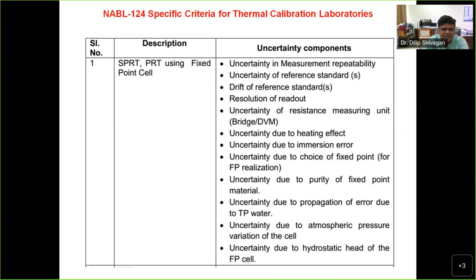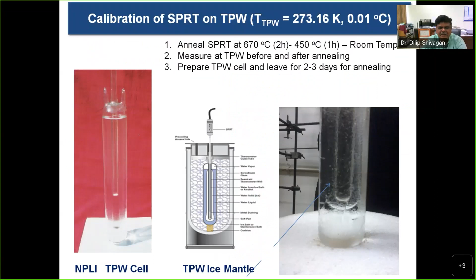So that you can estimate the drift. Platinum resistance thermometers are very good because they are very linear, but still you can see that at lower temperature they go toward the Debye temperature, meaning resistance will not increase linearly, and at high temperature also they will have some losses. So ITS 90 has given very standard equations for how we have to interpolate. Basically, you have to measure first at the fixed points and evolve these alpha, beta, gamma coefficients. If you put those in, then your measured temperature is very accurate. So these are the uncertainty components. These are mainly required for primary, but you can see that there are several parameters there.